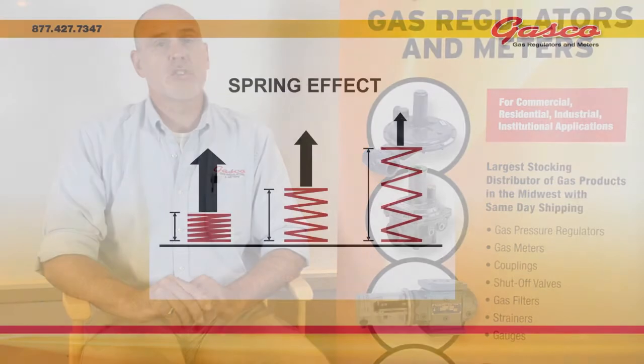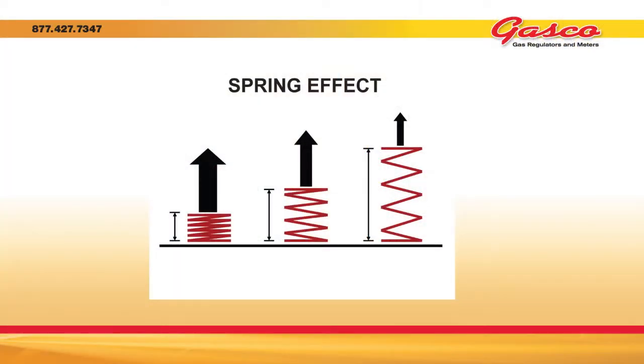The second reason for the regulator not to perform ideally is due to what is referred to as the spring effect. The spring will continue to open; however, as the spring opens, the coils are extending and the spring's force begins to diminish. The further it opens, the more it loses its force. Unfortunately, this is when the desired position of the valve is to be in a more open position, yet the spring is losing its ability to more easily open the valve.